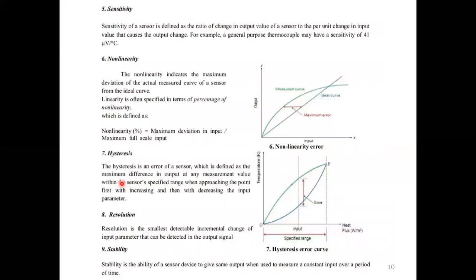So another characteristic is sensitivity. Sensitivity of a sensor is defined as the ratio of change in the output value of a sensor to the per unit change in input value that causes the output change. For example, a general purpose thermocouple may have a sensitivity of 41 microvolt per degree Celsius. That means per degree Celsius, that much voltage will vary. So for 1 degree change, the output will change by 41 microvolt.